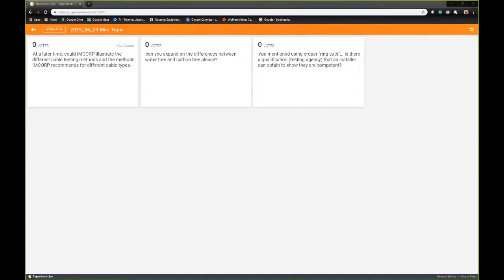We're on a cable for about 40 to 60 seconds. We go from operating voltage, we'll go to 1.3, 1.5, 1.7, 2 times operating, up to 2.5 times operating voltage. Typically, we don't go any higher than that because we are going to recommend surge protection. So the margin of protection on that cable system should never see over 2 times operating voltage. But any voltage on a cable can be devastating. It can be destructive. We just stay on it for a lot less time.